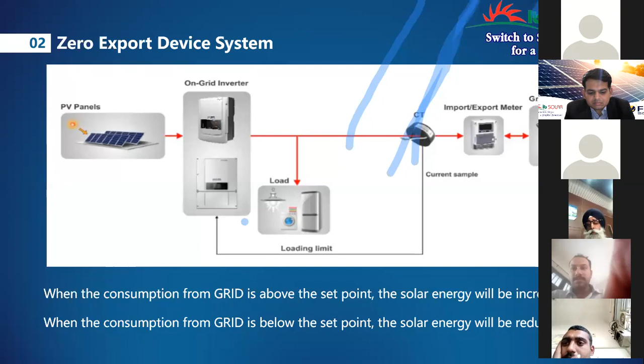When the consumption from the grid is higher than the set point in the inverter, the inverter will increase the generation. If the consumption from the grid is lower than the set point, the inverter will decrease the generation. The generation of the inverter is mainly regulated by changing the MPPT power. So the regulation of power generation is done by the MPPT technology of the inverter. That is inbuilt and is called the zero export function. Based on your load regulation, it regulates the generation of power from PV. Next.